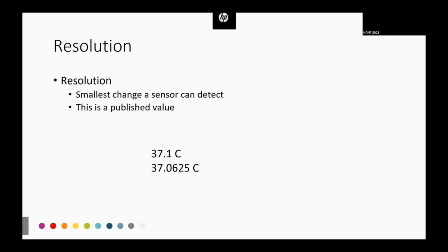For example, a sensor might give you a body temperature of 37.1 C, or a sensor might give you a reading of 37.0625. Both of them have the same accuracy. It doesn't mean the one with more decimals is a better or more accurate sensor, it just has more resolution, so you can see smaller steps.